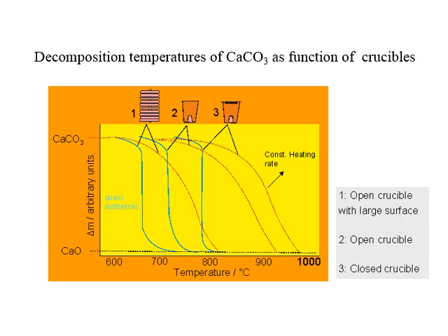case, if you actually put a lid of some type on the crucible, you will increase the reaction temperatures because you're creating a localized partial pressure of the evolved gases. So the crucible matters. In general, in TGA though, it's generally just some type of an open pan or open crucible.